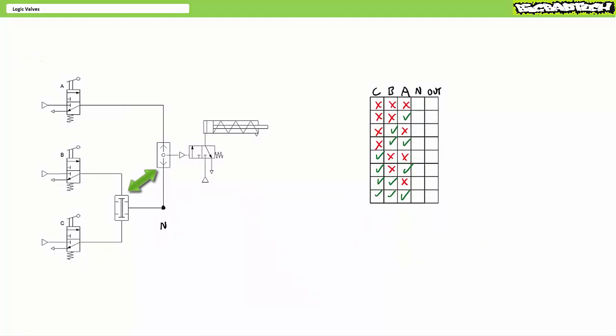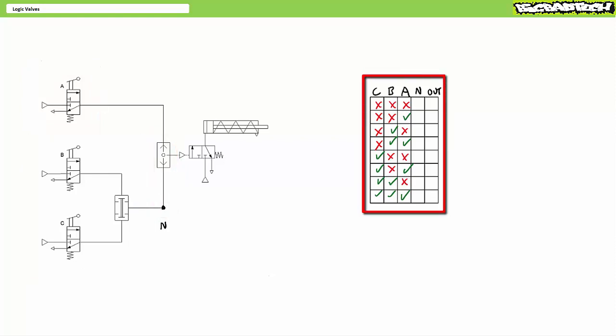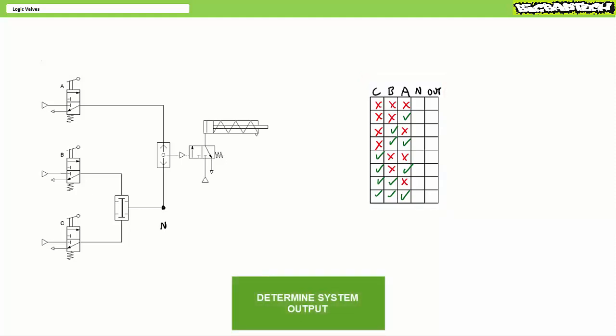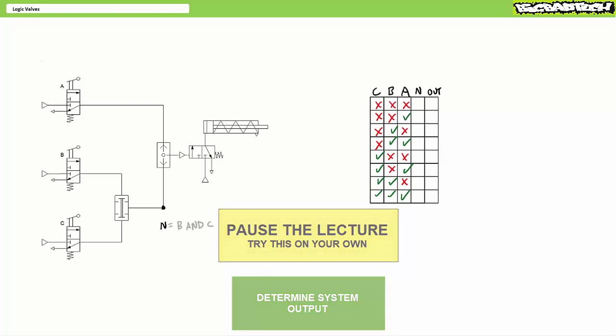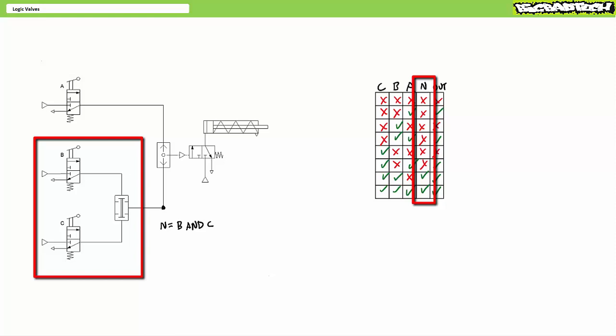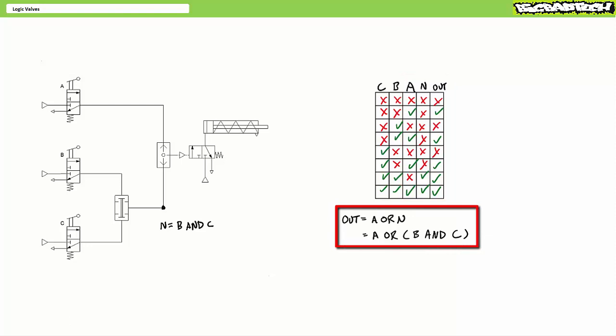Consider a subtle change: all I've done is swap the connections to the logic valves. Now A is being ORed with the output of the AND valve, which has inputs B and C. Using the brute force technique again with eight possible scenarios — and including an intermediary output of just the AND valve as pilot signal N — the AND valve produces output at N only when signal is present at both B and C. The OR gate then produces an output when there is a signal at either A or N. This system is performing the function A OR (B AND C), with the AND operator resolved first as intermediary output N before being ORed with A.